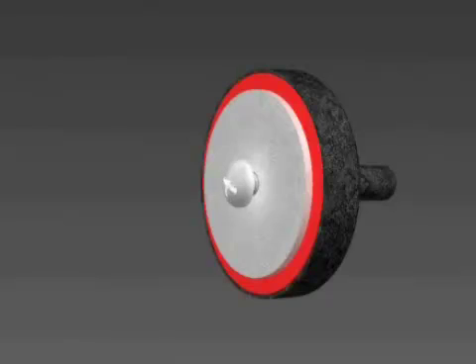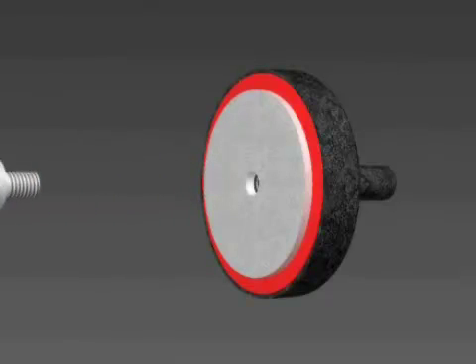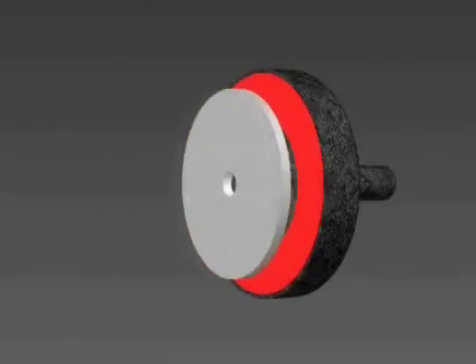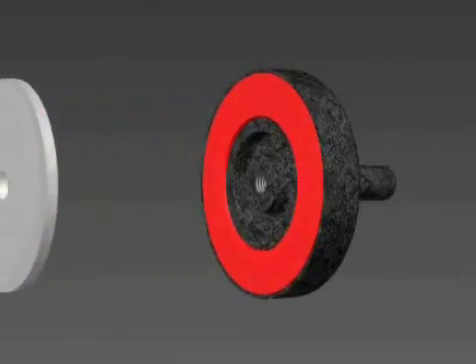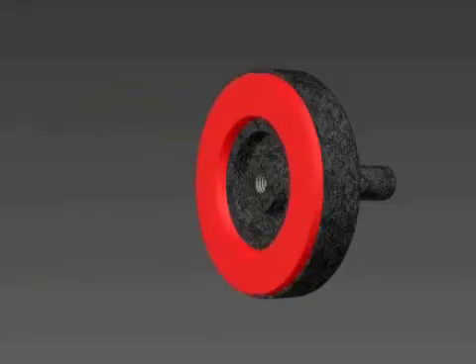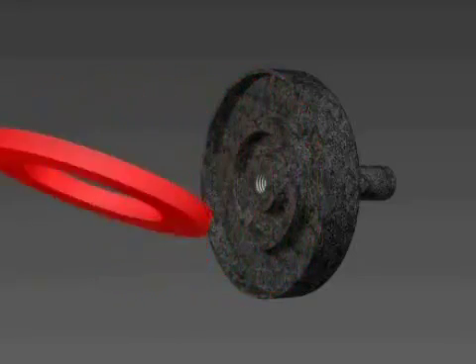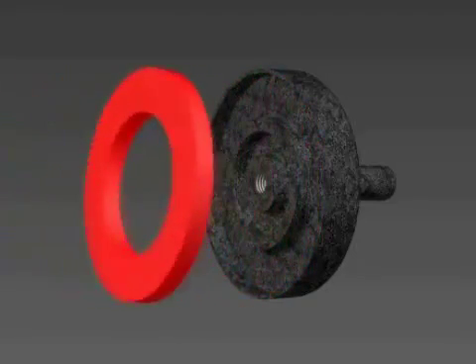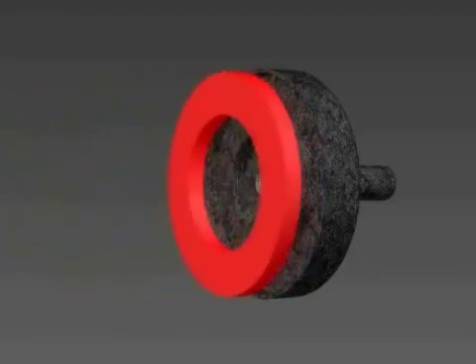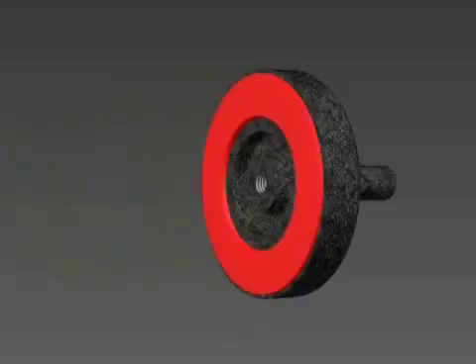To remove a damaged seal ring, remove the screw and retaining washer. For a temporary fix, you can flip the seal ring over to use the smooth side while waiting for your new replacement parts.